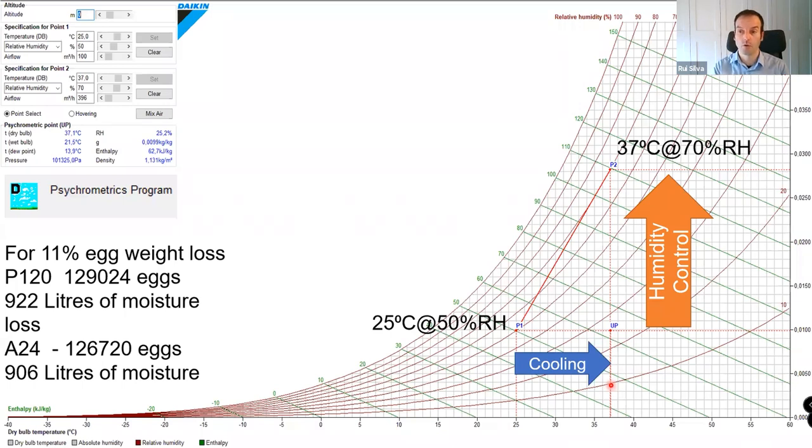How the machine will cope with it, or it will work on your damper, it will close the dampers, therefore it will not allow enough air for the CO2 and O2 exchange that you want. So in order to control the humidity, you will fight against the O2 and the CO2. So if you work on the other side, if you put too humid, you don't have that much capacity in the air to absorb that much humidity that you would like.